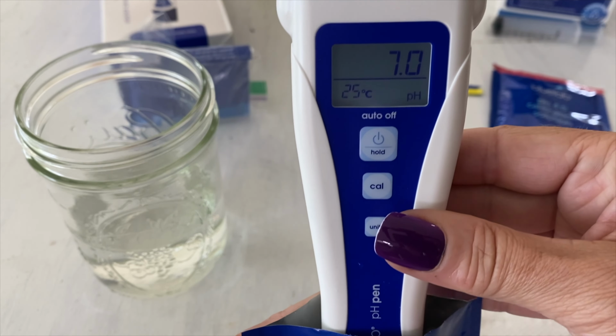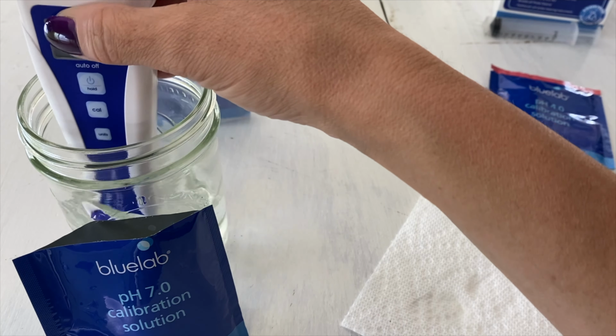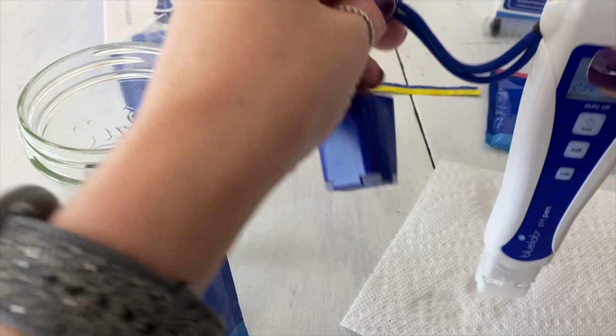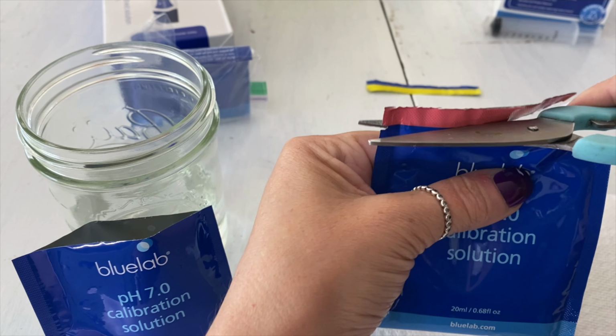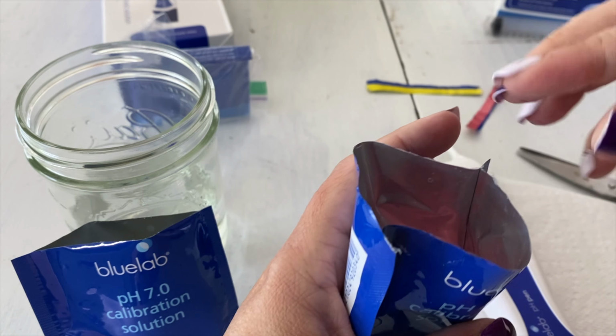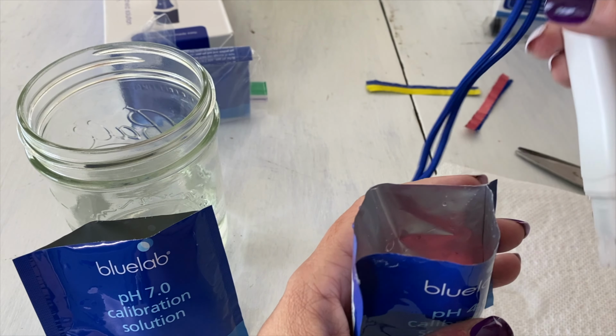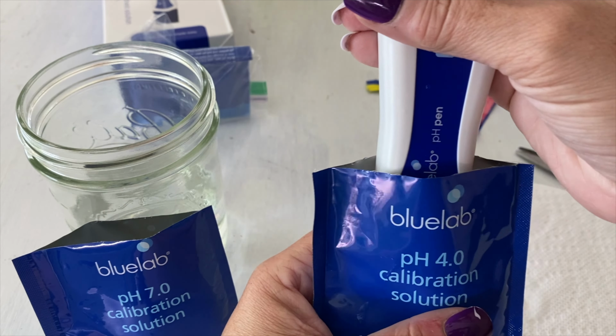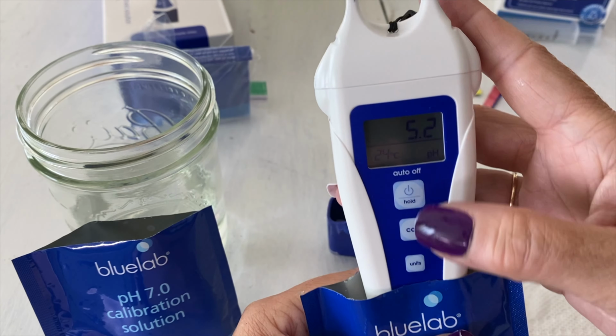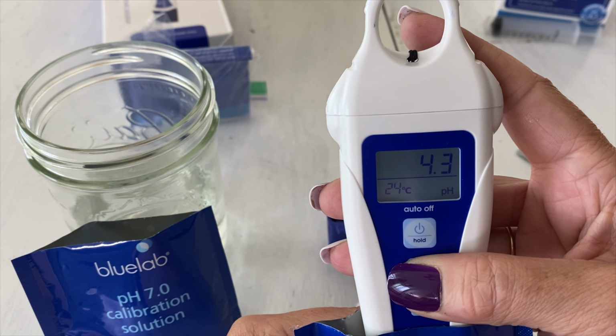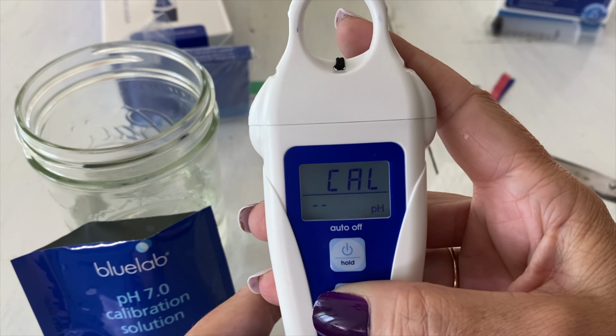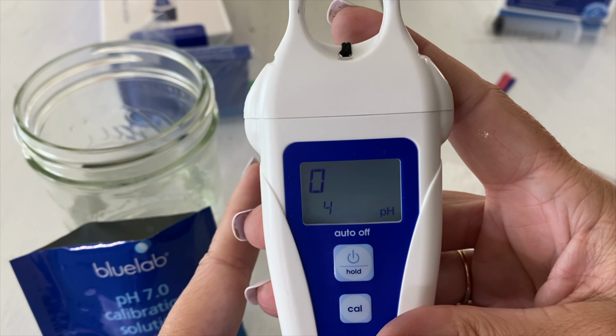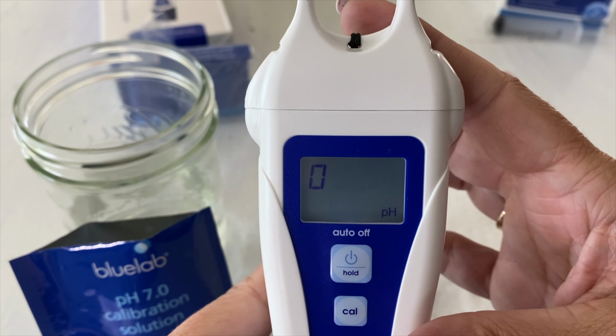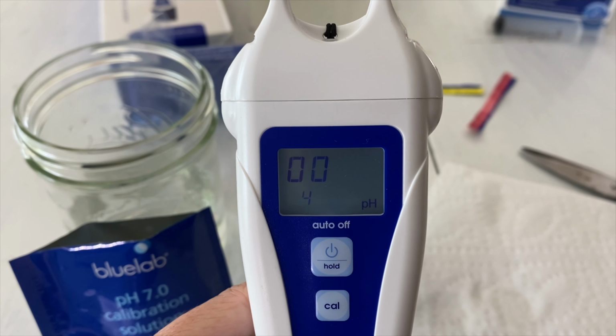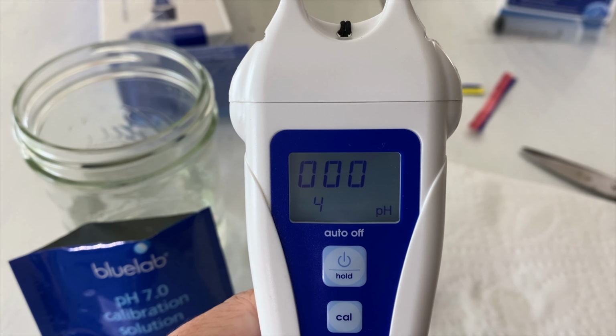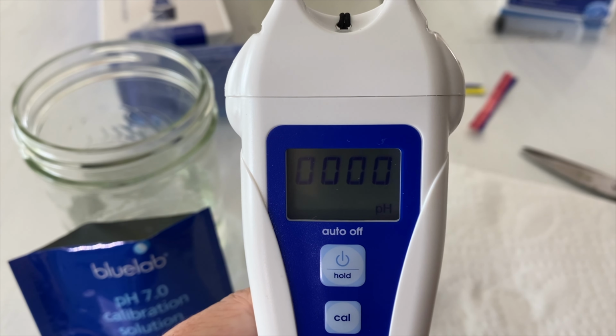Then you're gonna rinse it off, and you're gonna do the exact same thing with the 4.0. Cut off the top and stick it in. I also noticed this one had a little bit of a pink color, so if you put it in a different container, you should be able to tell the difference. Go ahead and push and hold your calibration button once again. It will tell you it's calibrating and go into the 4 zeros that you're looking for. Once it's hit those 4 numbers, then you've got a perfect calibration of the 4.0.